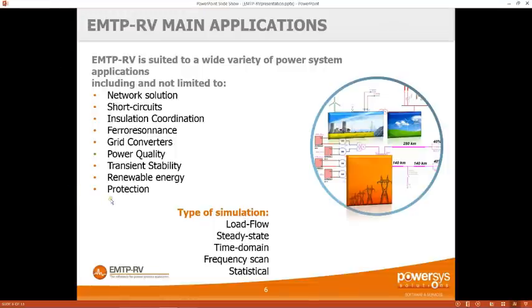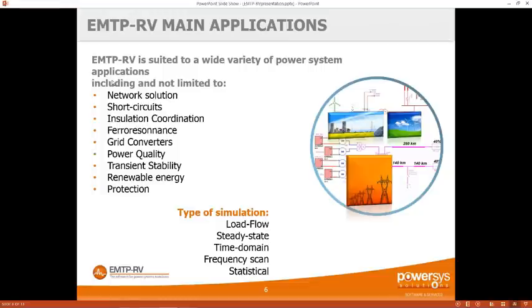Here are the main kinds of simulations we can use EMTP-RV for. Starting with the network solution: the inputs are all the power constraints of the network — for example, the load which can be PV or PQ, the machines that produce power set as PV or PQ, and the slack bus. The software runs a load flow simulation and finds the voltage, angle, power, and current everywhere on the network.